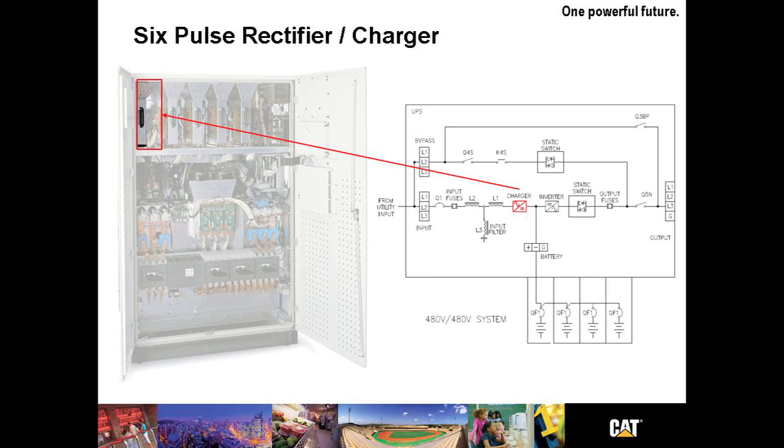If the frequency should drift out of tolerance, the charger will shut down. The charger is sized to recharge a battery providing 30 minutes of backup time. The only constraint on the charger are related to the thermal characteristics of the three phase inductors and the charger. DC ripple is held to less than 1% of the DC voltage RMS value.